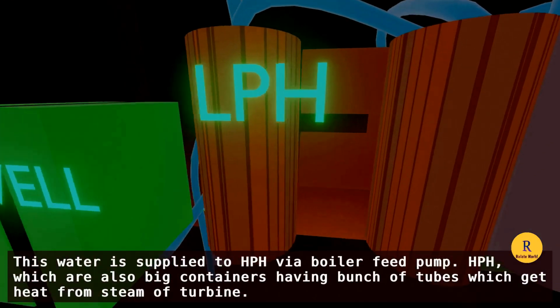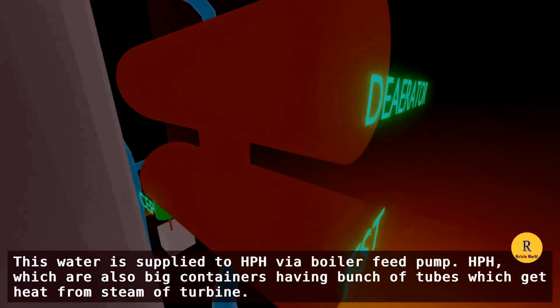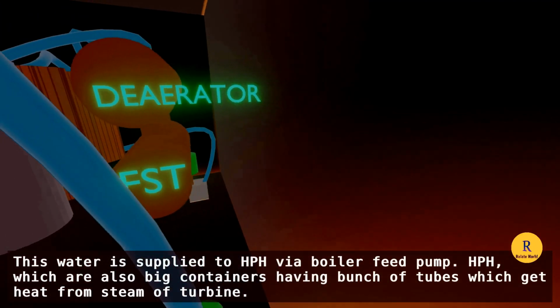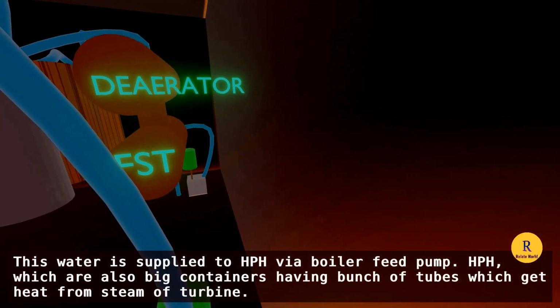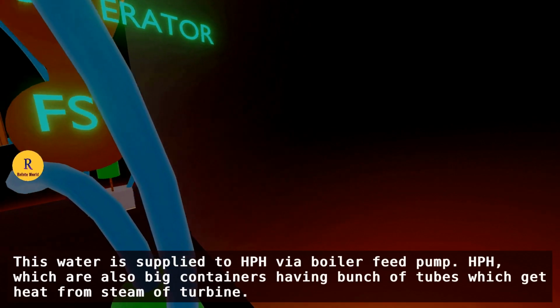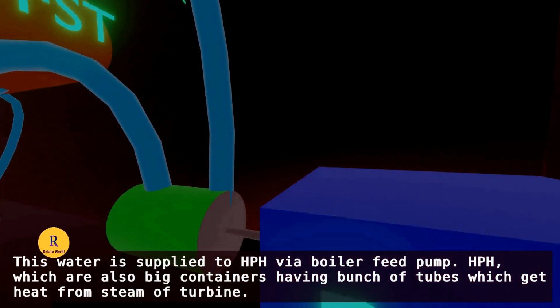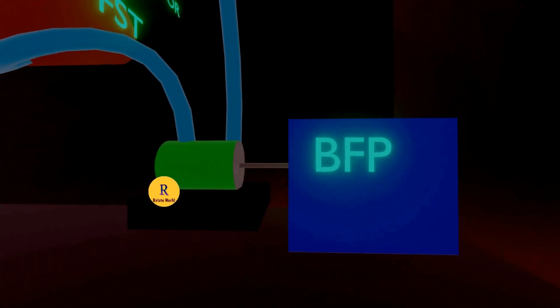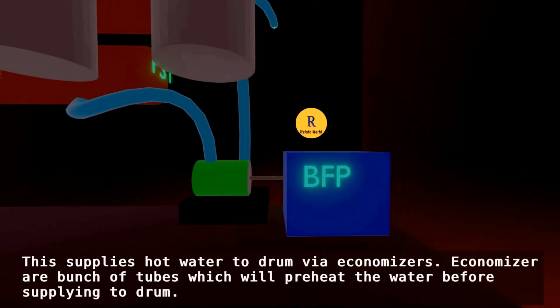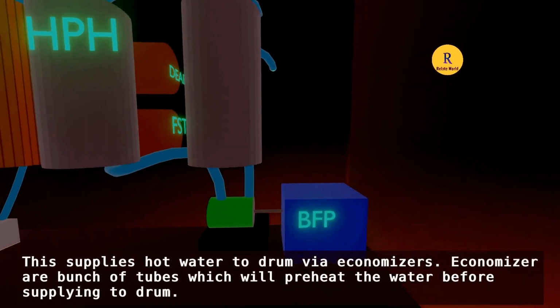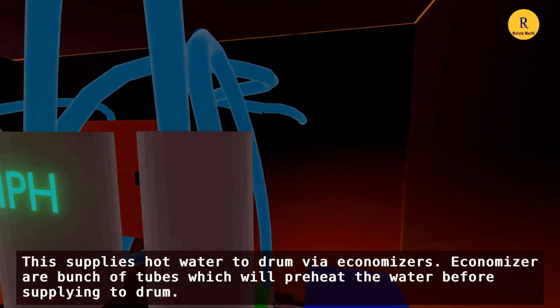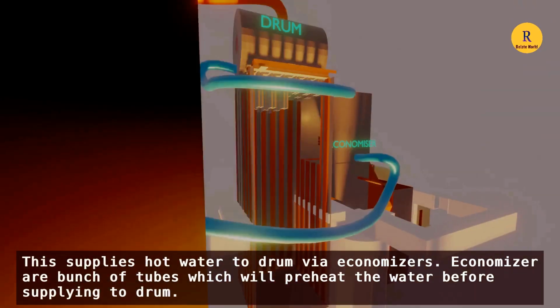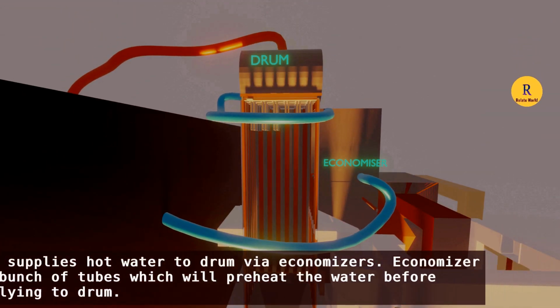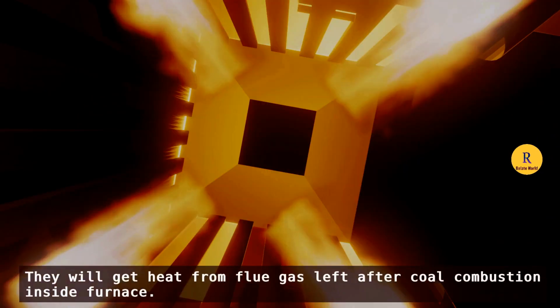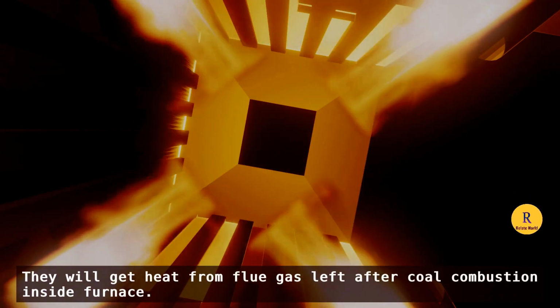This water is supplied to HP heater by a boiler feed pump. HP heaters are also big containers having bunch of tubes which get heat from steam of turbine. This supplies hot water to drum by economizers. Economizers are bunch of tubes which will preheat the water before supplying to drum. They will get heat from flue gas left after coal combustion inside furnace.